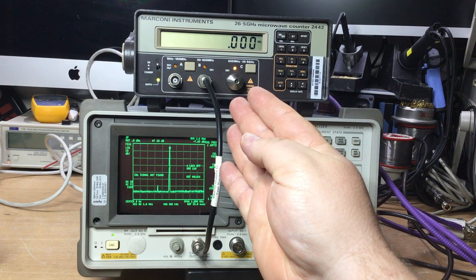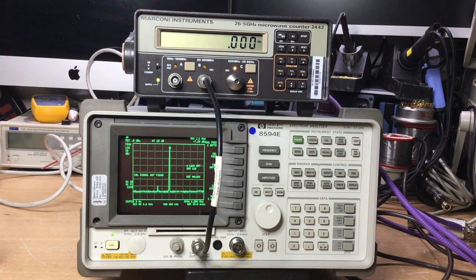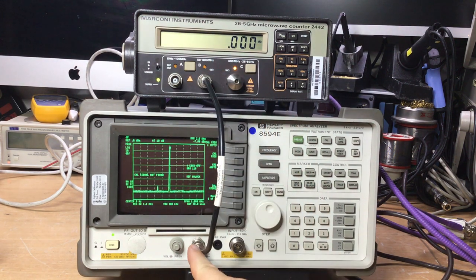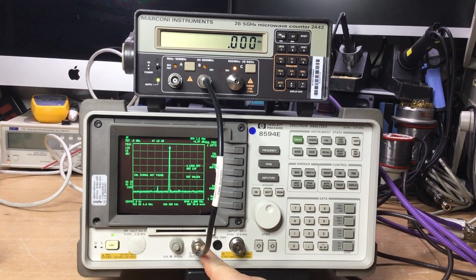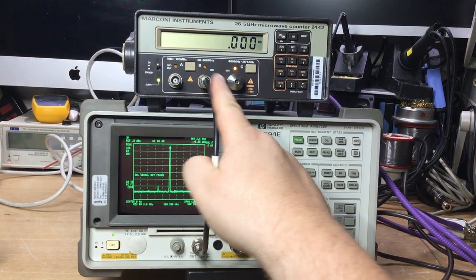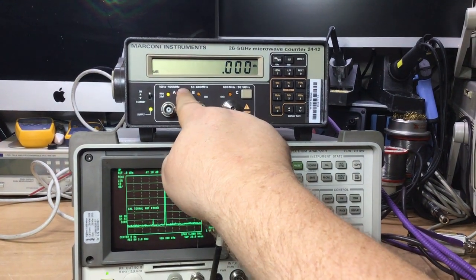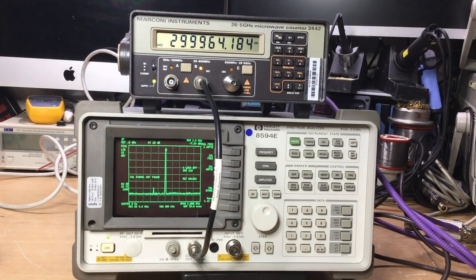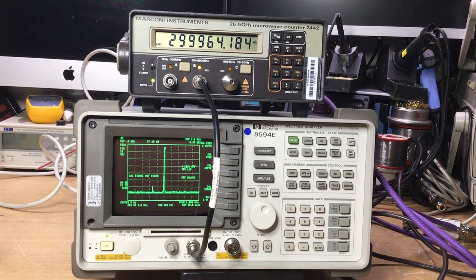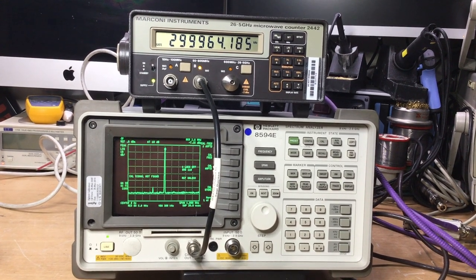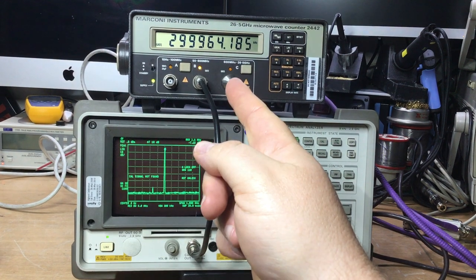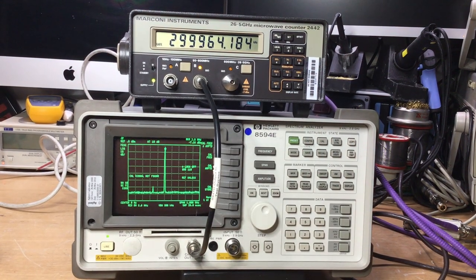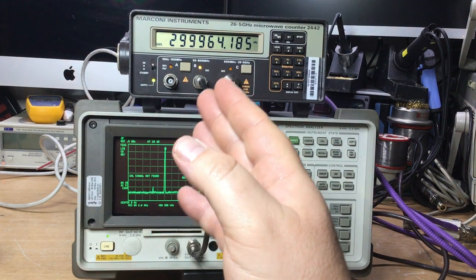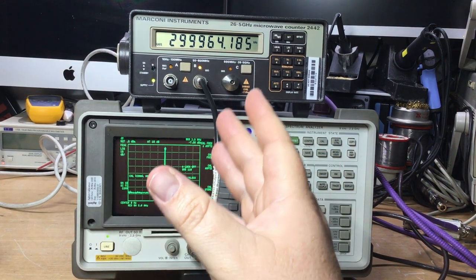So we've got a Marconi Instruments frequency counter, which goes up to 26.5 gigahertz. We're going to use the B input, because 300 megahertz at minus 10 dBm is what emanates from this BNC. So we're going to select B on there, and then it'll display the calibrate frequency. Now it should be 300 megahertz spot on. Now before you do any frequency measurement, this is a calibrated Marconi frequency counter, and it's on its own internal standard at the moment, which has been calibrated.